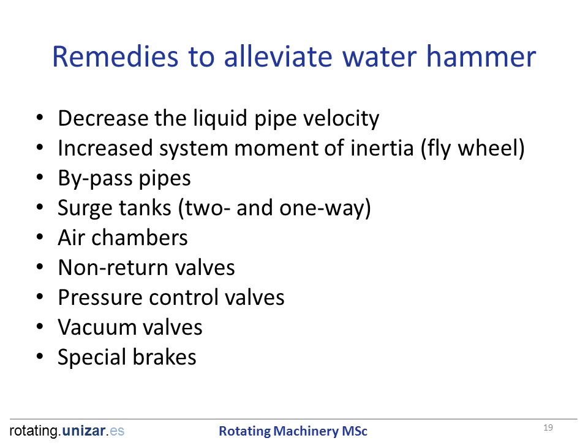These are some remedies to alleviate water hammer. One can change the design to decrease the liquid pipe velocity, or use systems with an increased moment of inertia with flywheels, or use bypass pipes or surge tanks — which can be two-way or one-way — air chambers, non-return valves, pressure control valves, vacuum valves, and special brakes.